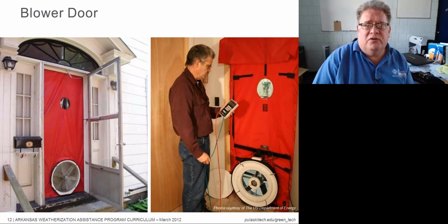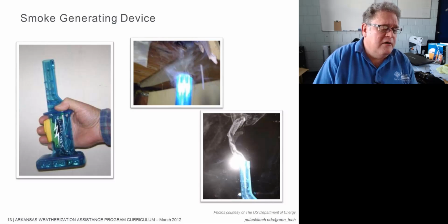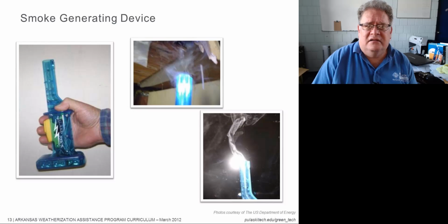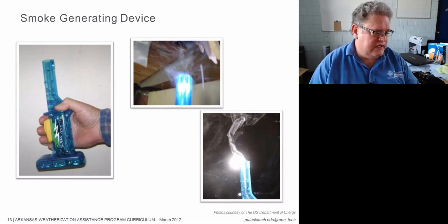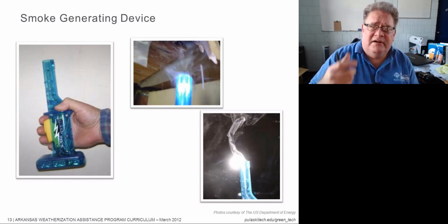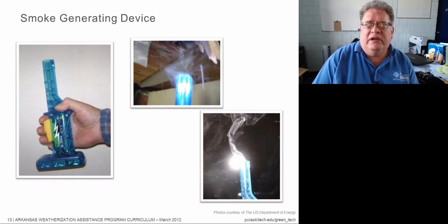Then you want something to create smoke. You want to carry something so that you can make some smoke. Now some folks love these things and some folks hate these things. They are a non-toxic smoke generator, meaning that the smoke that they create is non-toxic. Some of the older puff ones use a chemical that is buoyantly neutral in air. It won't rise or fall because it's the same temperature as the air. So it will move with the air. Whatever air you put it into, if that air is moving up, it's going to move with it. If that air is moving down, it's going to move with it. It's not going to rise or fall on its own.